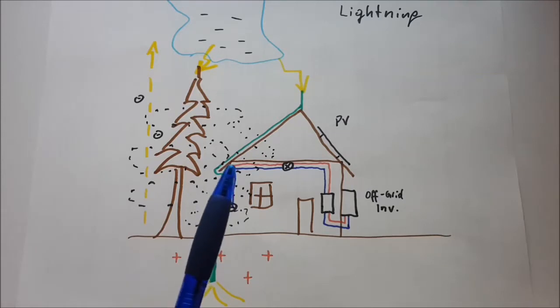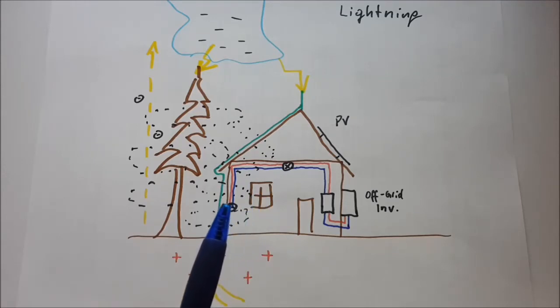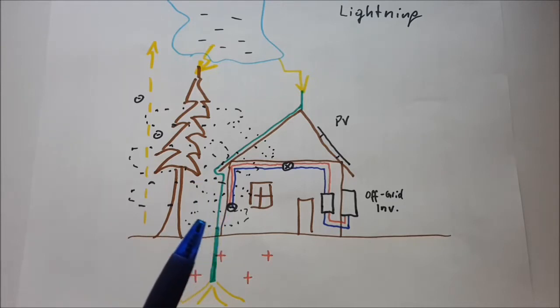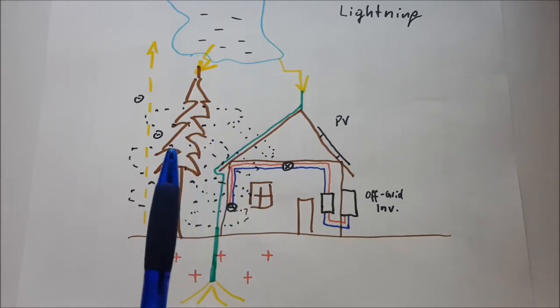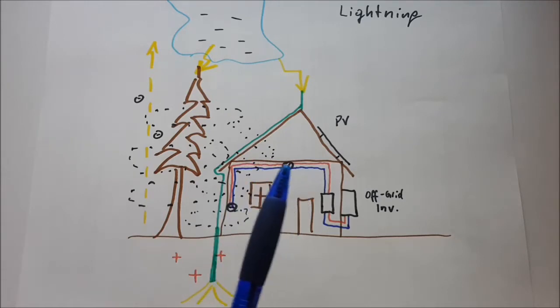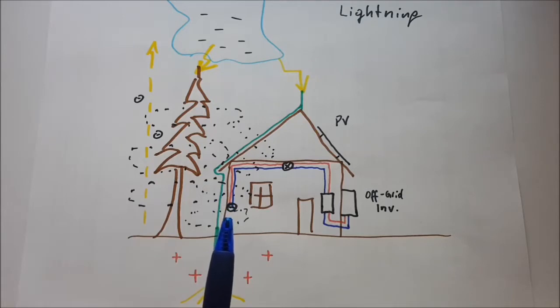What happens now when a magnetic field is coming into contact with wiring? We have our wiring inside our installation. We know that from equipment like transformers: every time when you have magnetic fields and wiring, we have a primary coil and a secondary coil, which will be our wiring here. Voltage is generated on the secondary side. The current traveling through our lightning arrestor or tree will induce a voltage on our electrical installation just because the magnetic field is hitting our copper wires there.